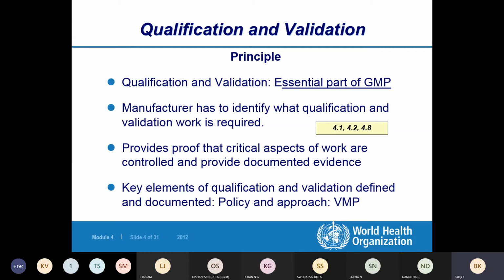If you want to validate your chamber, okay, inoculation incubator, we call it an incubator or chamber, then you have to validate at setting at 20 to 25 degree, and then 30 to 35 degree, and 50 to 55 degree as well. So when you keep the temperature setting, you have to verify that all the places inside the chamber, okay, based on the volume. So if it is like 300 volume, it is verified that the complete chamber has been tested for the purpose of temperature distribution. Okay, the temperature is distributed and maintained at a required condition. So that is the purpose of validation.